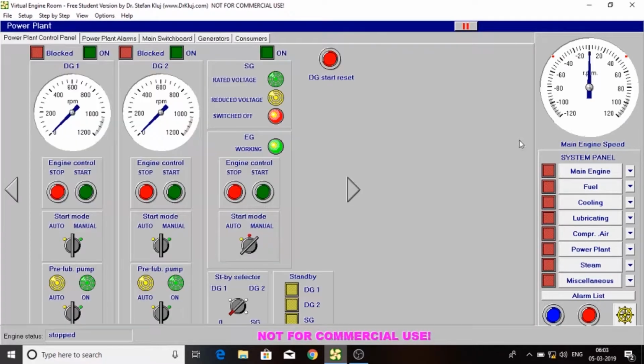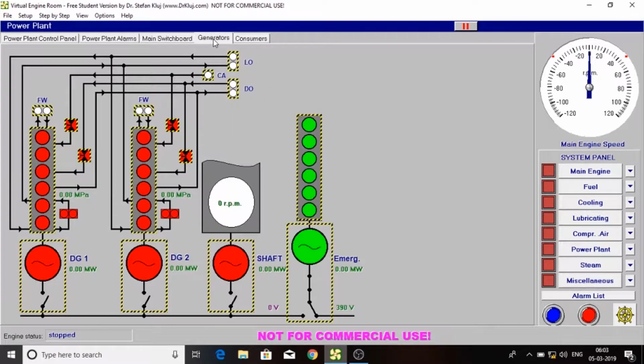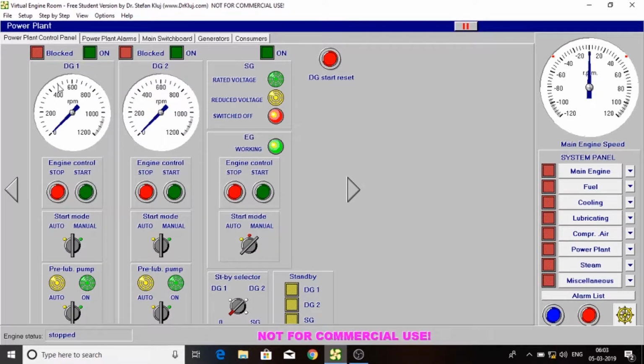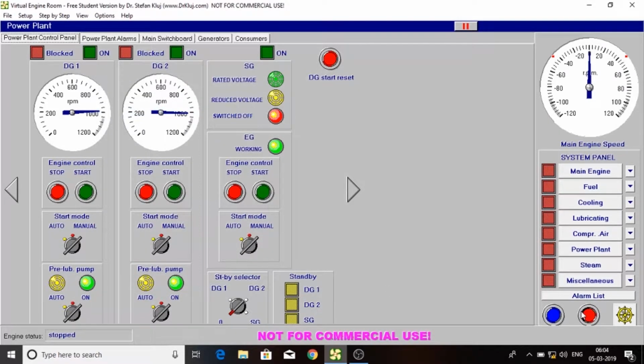Now let's again go to the power plant to start the diesel generators. Open the air intake valve and fuel intake valve for both DGs. Select the start mode to manual and turn on the pre-lub pump, then start. Turn the pre-lub pump to auto.